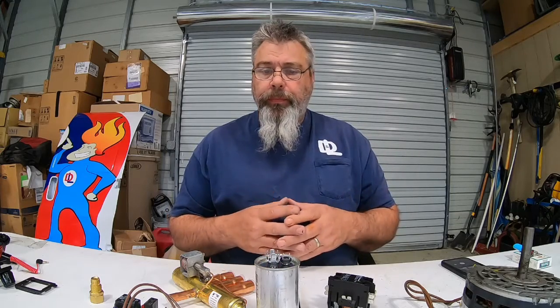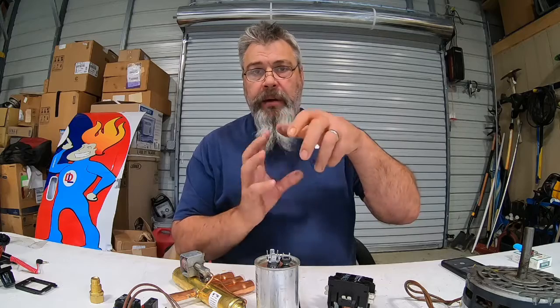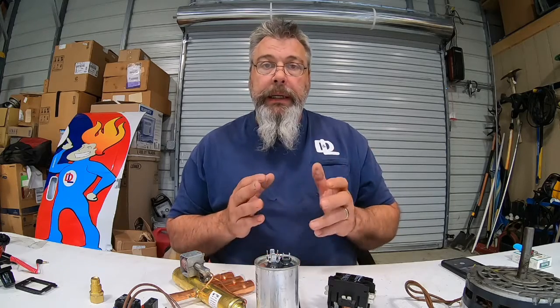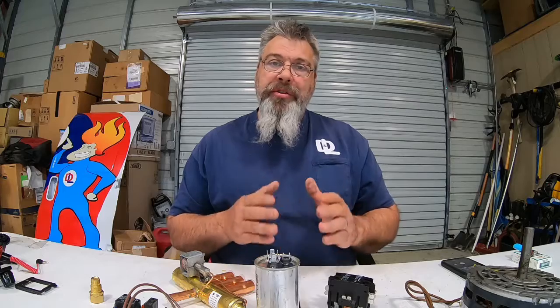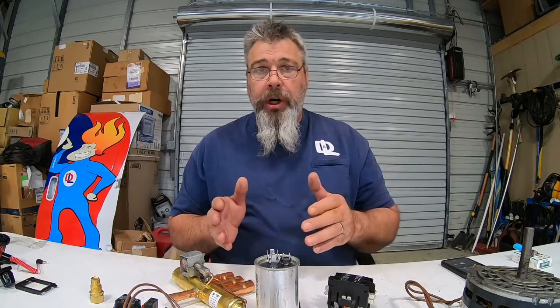They have many different ones now, but the most common one is a scroll compressor. It has plates inside that move back and forth. It actually compresses the refrigerant. And I'll probably get a lot of people saying, oh, it can't do that. Yes, it can, as long as it's a gas. You can't compress liquid. Nobody can. Doesn't work in automobiles. It's not going to work in a compressor for your AC or heat pump.